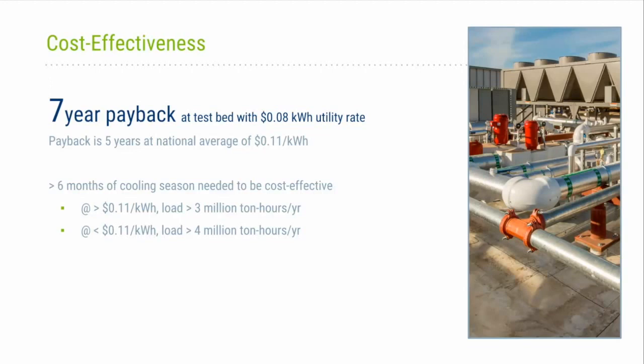Again, based on the savings we saw, about $42,000 for the chilled water plant per year, that comes out to be about a 7-year payback at the utility rate of 8 cents a kilowatt hour. If your utility rates are higher, obviously your payback will be sooner, assuming you have a similar plant, similar performance. So based on those numbers, the optimum that we came up with would be if you had on average a 6-month cooling season at utility rates greater than or equal to 11 cents a kilowatt hour, then you'd need at least 3 million ton hours a year to be cost effective for this technology to approach that level of payback. If you have lower utility rates, it's going to obviously take longer.